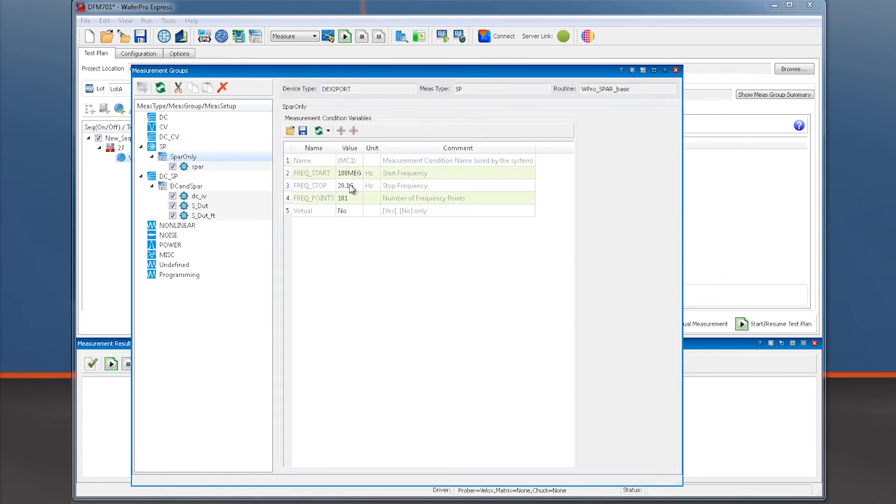Here again, we need to align the frequency start, stop, and number of points to our network analyzer stimulus settings during calibration.